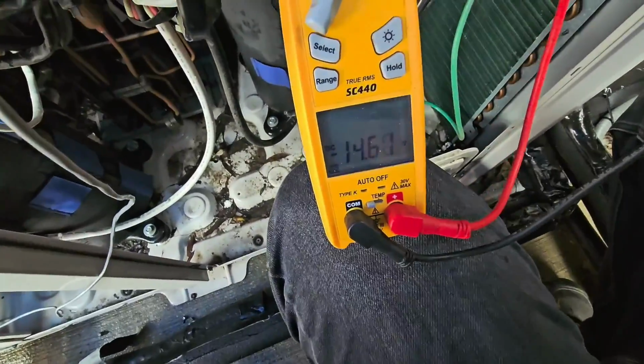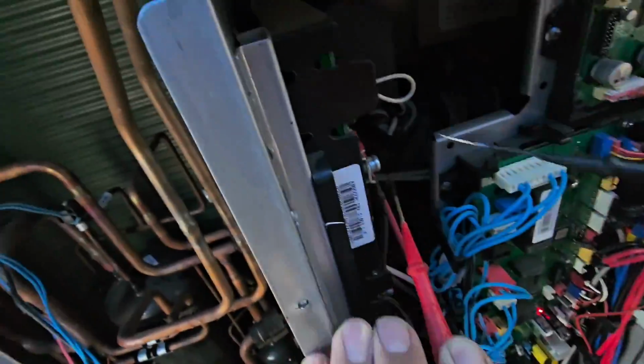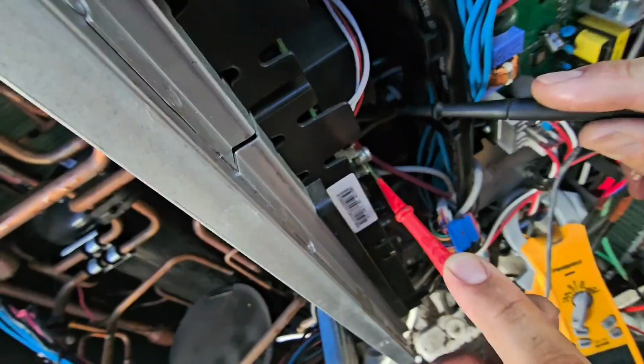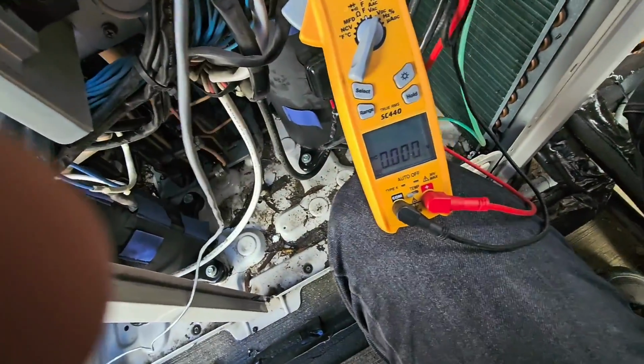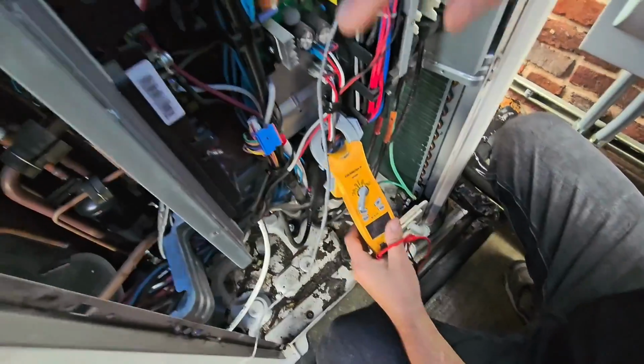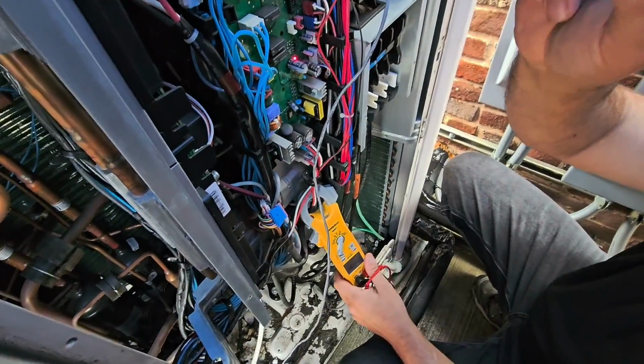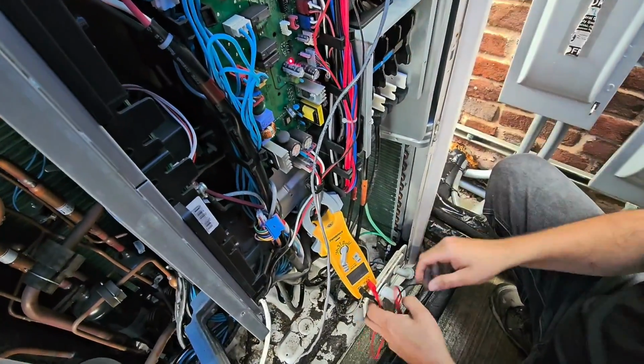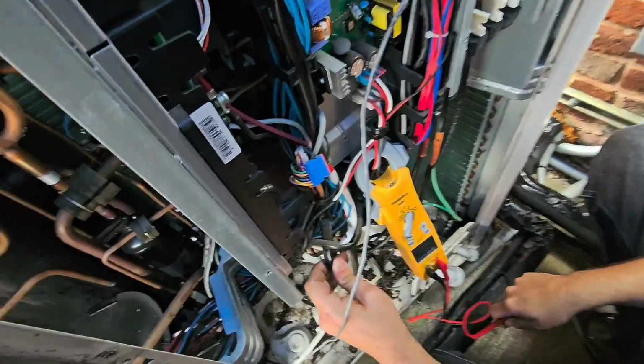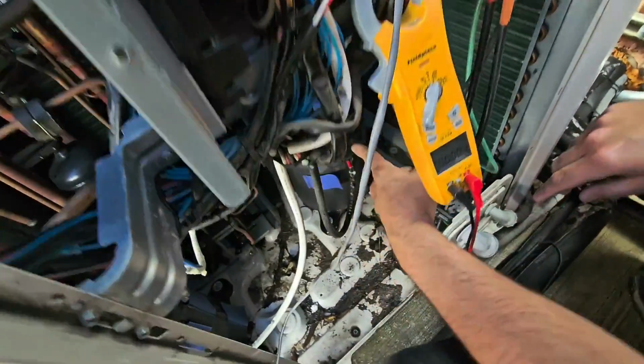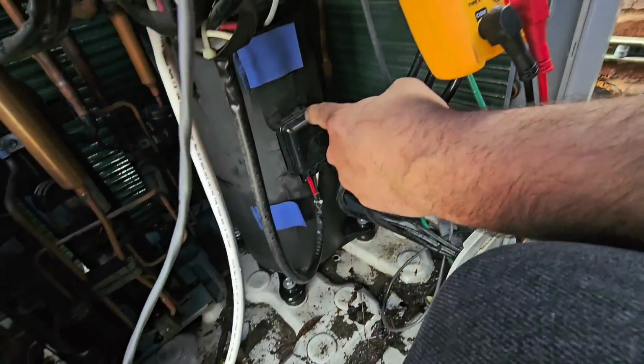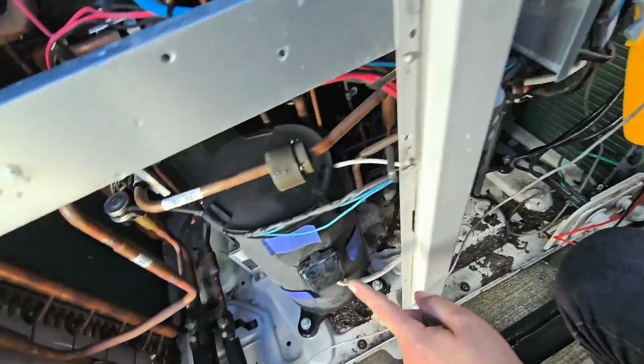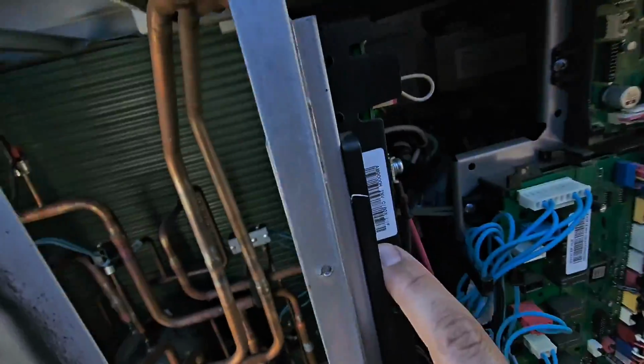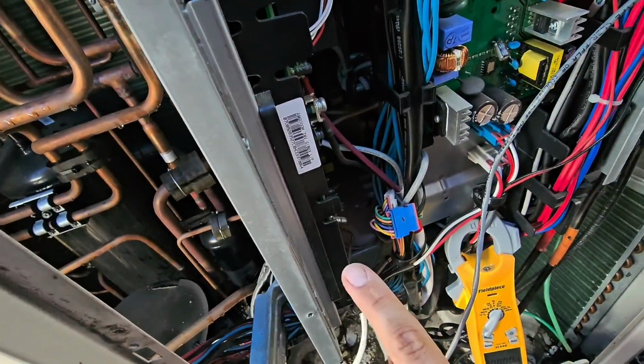14 volts. Now let's go down here to the black and red wire on the other inverter board, checking the DC. What do we got? 0. So that means from top to bottom, this must be inverter number 1. And if you follow the wiring, this is compressor number 1 right here. So that's compressor number 1, that's compressor number 2. Inverter board number 1, inverter board number 2.